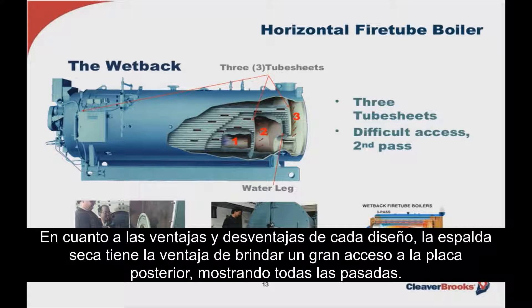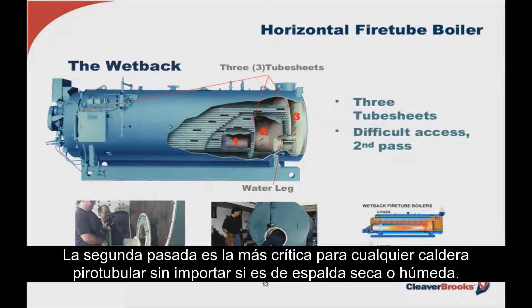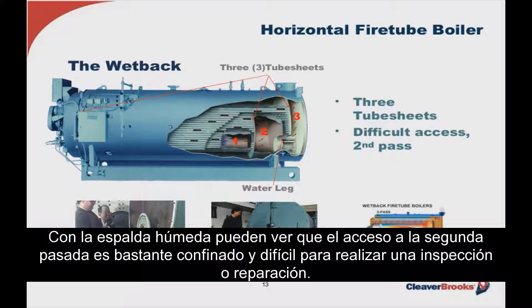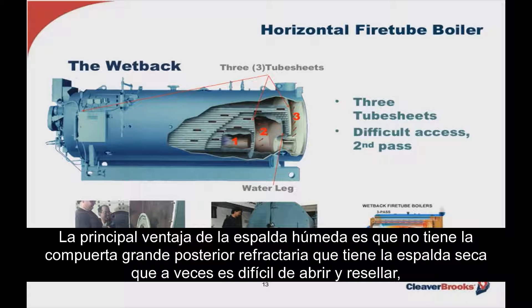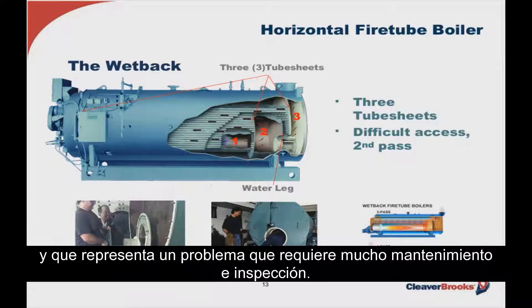As for advantages and disadvantages: the dry back has the distinct advantage of providing easy accessibility to the rear tube sheet, revealing all the passes — the second pass being the most critical in any fire tube boiler. With the wet back, access to the second pass is very confined and difficult to work in when inspecting or repairing. The main advantage of the wet back is the elimination of the heavy refractory-filled rear door found on the dry back, which is sometimes cumbersome to open and reseal and is an ongoing inspection and maintenance issue.